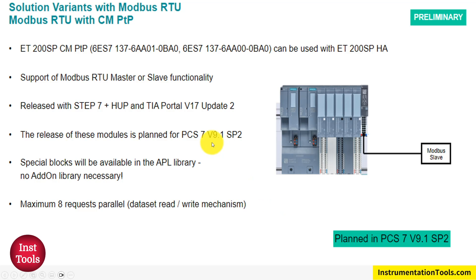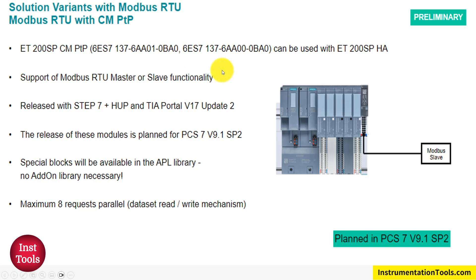When connecting with ET200M or ET200SP, there is another solution which also serves as a Modbus RTU master. The ET200SP CM PTP module can act as both master or slave. The communication line is the same as the previous slide and it communicates with RTU slaves. The maximum number of parallel data requests supported is 8, so if you have 8 slave devices, it can poll all 8 devices simultaneously.